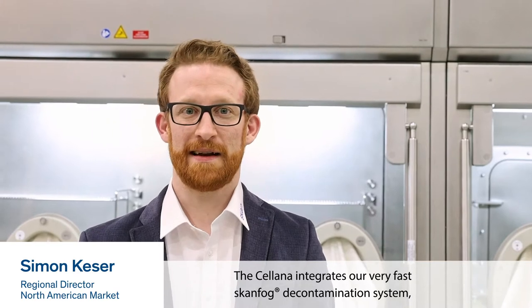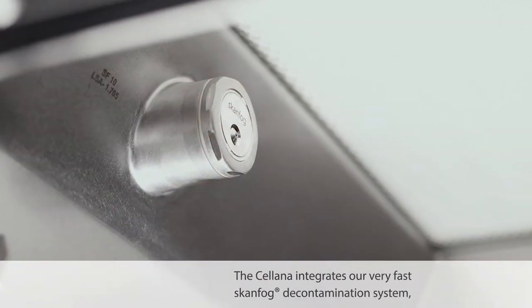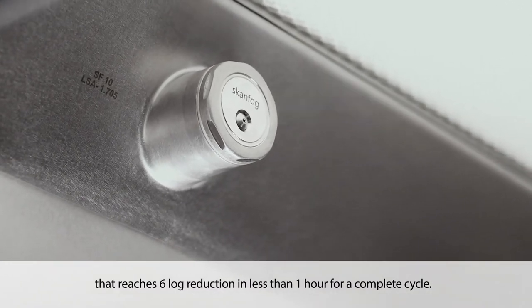Can you tell us more about the Skan latest decontamination and air flow technology inside the Cellana Isolator? Absolutely! The Cellana integrates our very fast scanfog decontamination system that reaches a 6-log reduction in less than an hour for a complete cycle.